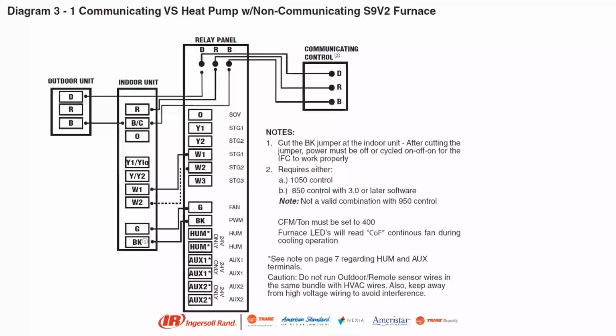I put this in here because we want to stress the importance of the relay panel with an S9V2, communicating S9V2. So we have a communicating control. I get this a lot. We're still getting a lot. We trip out on high head pressure. We run our communicating wires into the relay panel.